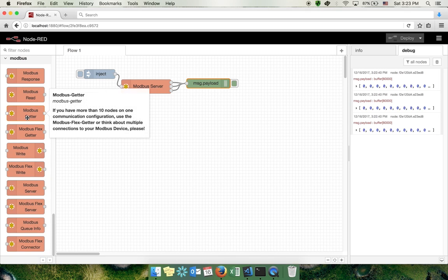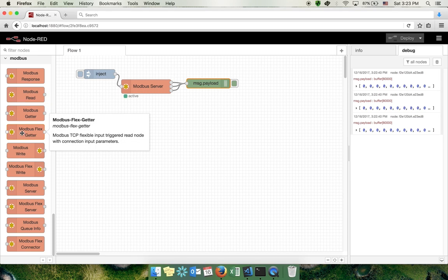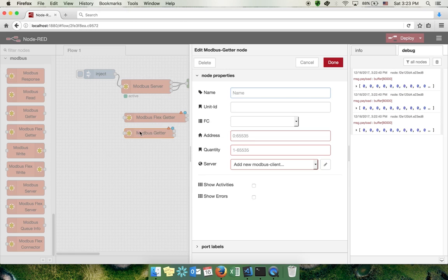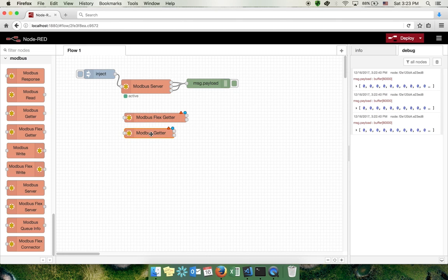So here you can see there are two readers. This one is called Modbus Getter and Modbus Flex Getter. I will strongly recommend using the Flex Getter. The main difference, as you can see, I can show them to you, is that the Getter is simpler because usually you will only need to complete this part to read a specific register, but it's kind of slow and sometimes it crashes.